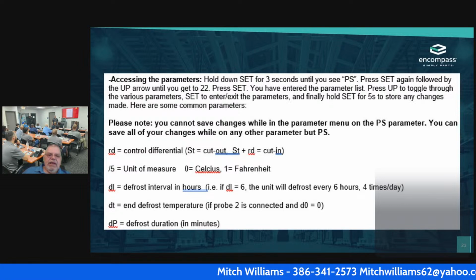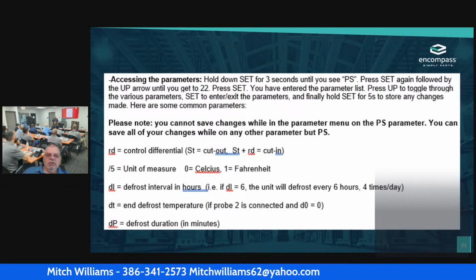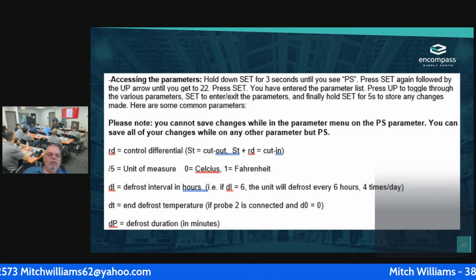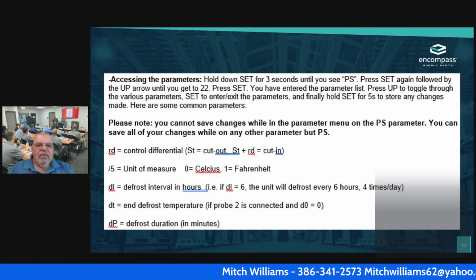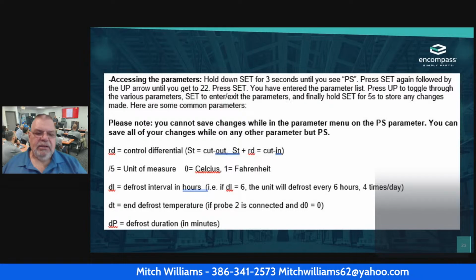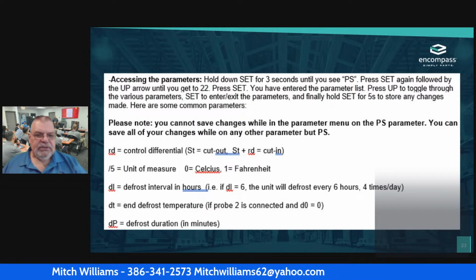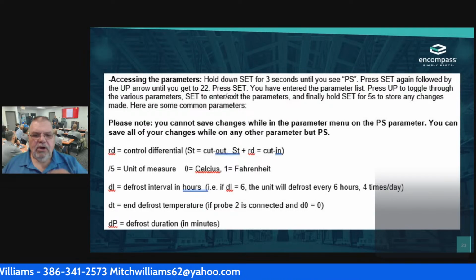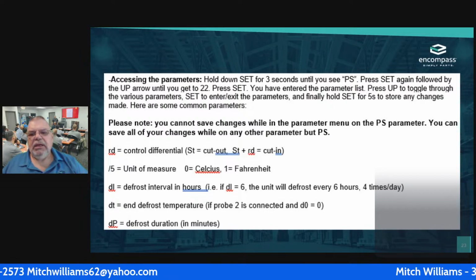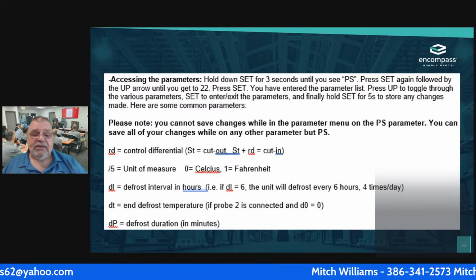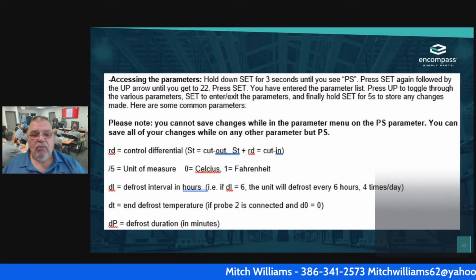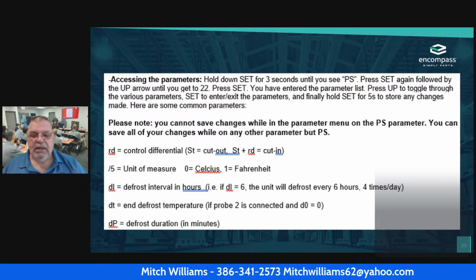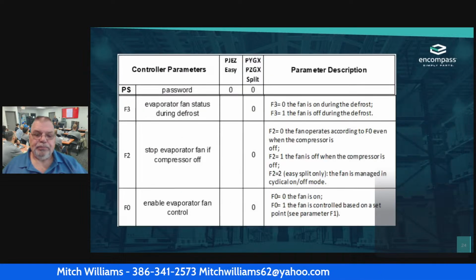So my DL is the defrost interval in hours. Okay. And then my DP is my defrost duration in minutes. So that's how long the defrost is. Of course, the defrost interval, I think it comes factory set at 6. So that would be 4 times a day it would go into defrost.